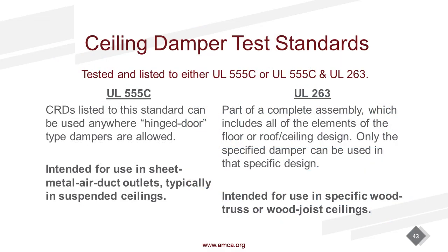So one thing that's important, ceiling damper test standards. Ceiling dampers and fire dampers are not the same thing. They both have fusible links. They're both tested by UL, but they do not do the same thing. As I told you, fire dampers prevent the spread of flame. Ceiling radiation dampers prevent the spread of radiant heat. So if I have a requirement where a ceiling damper is required by code, I cannot substitute a horizontal curtain fire damper. Now somebody in here just shook their head because they said, I just did that yesterday. It happens every day all over the country.